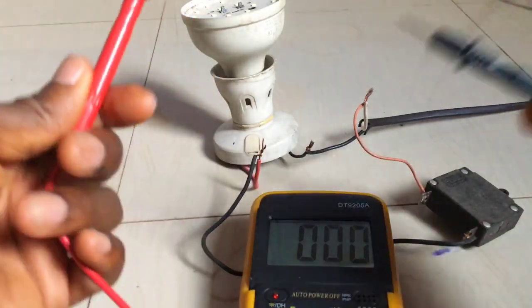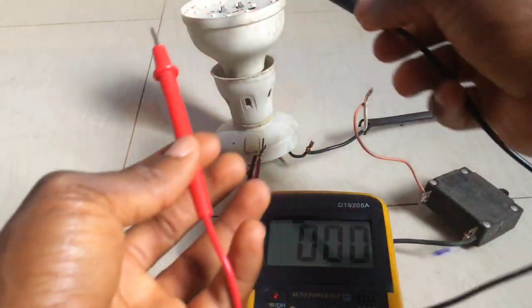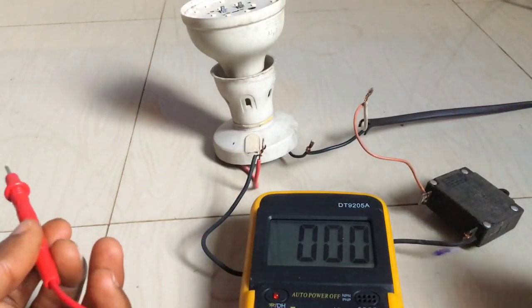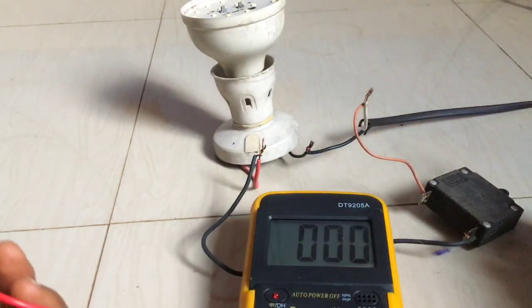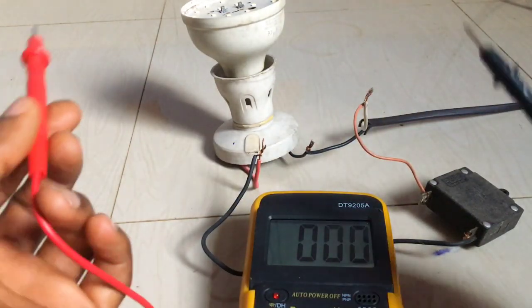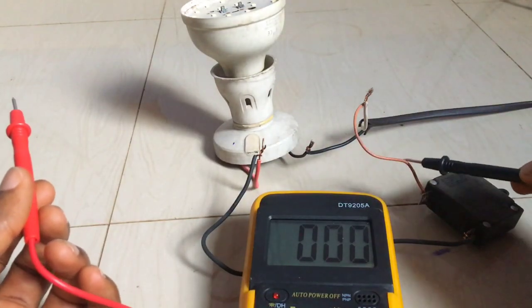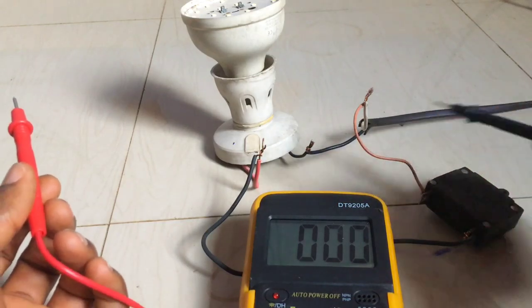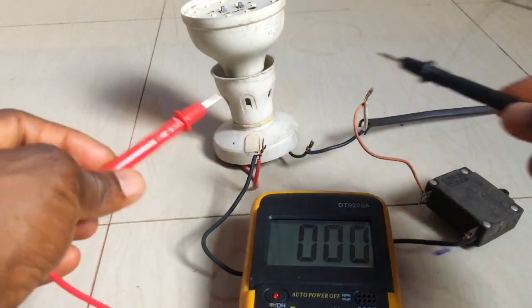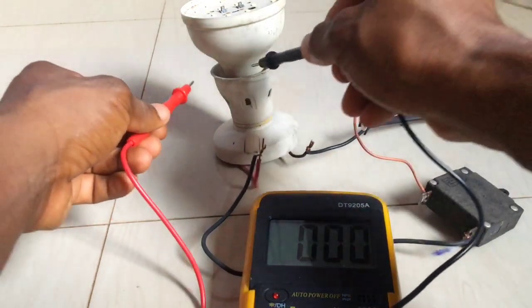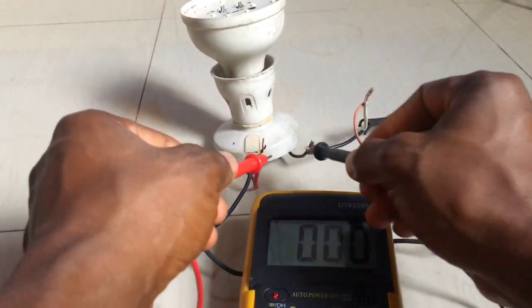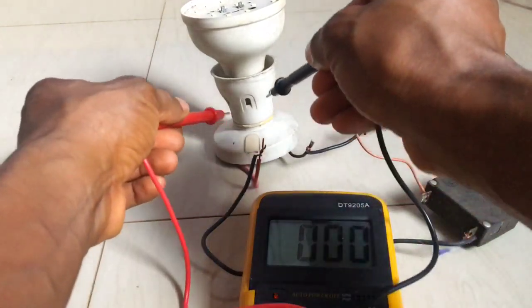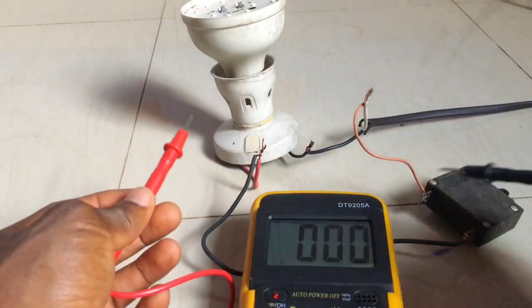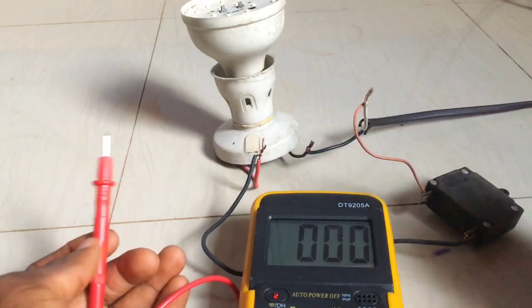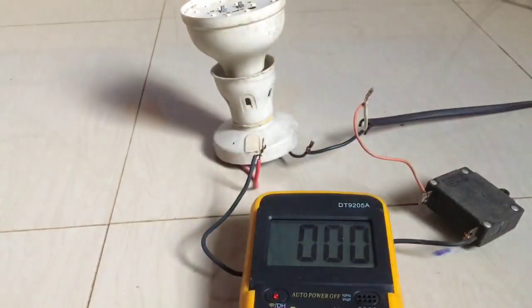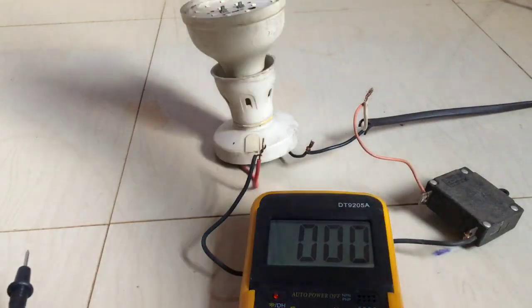But the most basic challenge you will be facing is replacing a dead lamp, changing a lamp holder, or replacing a bad switch. It's very rare to find a situation whereby the supply line from the circuit breaker is having issues, unless there is a problem. Sometimes a lamp holder may be bad and this terminal may breach internally, causing the breaker supplying this very cable to trip from the distribution board. So this is just a summary of how to troubleshoot lighting point issues.